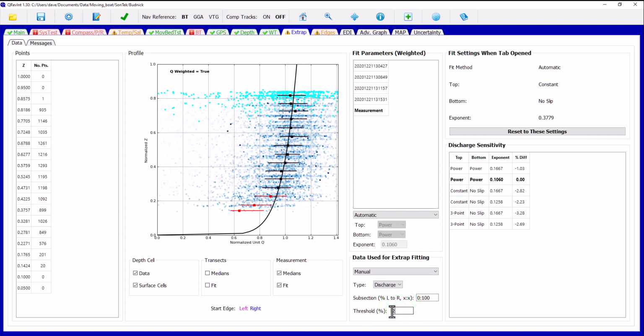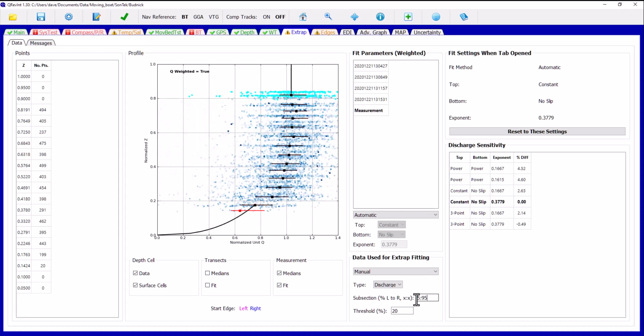That value is unreasonable. I wouldn't normally make that change. I did it here just to show the example. And again, for this rather unusual case, I would probably set 5 and 95, and then I would use the automatic fit. And I might downgrade the measurement when we look at uncertainty, because the uncertainty here is rather substantial.